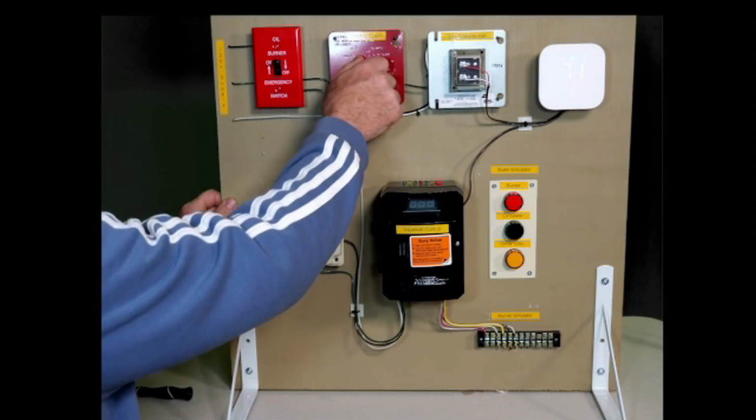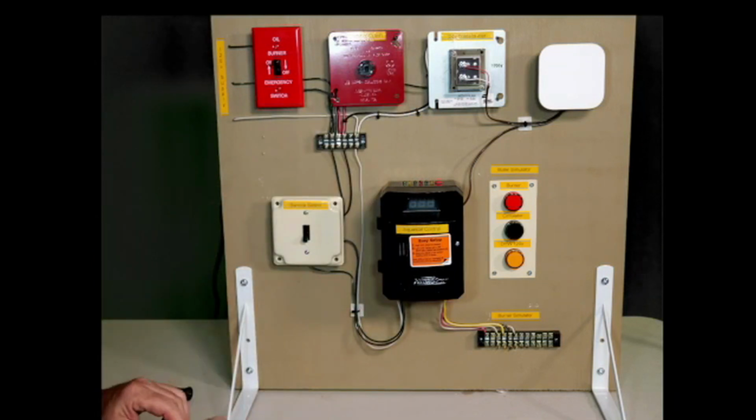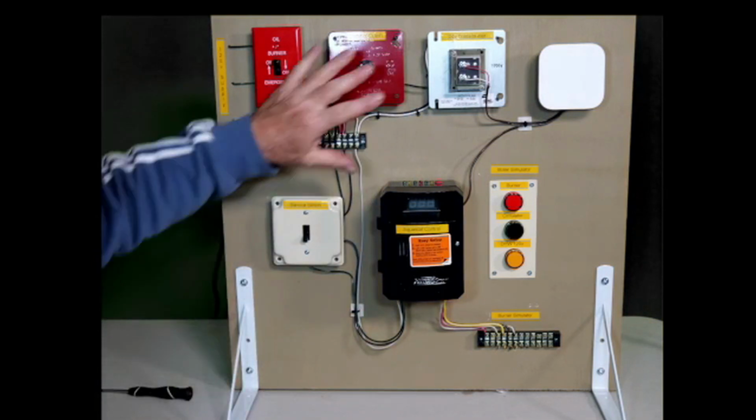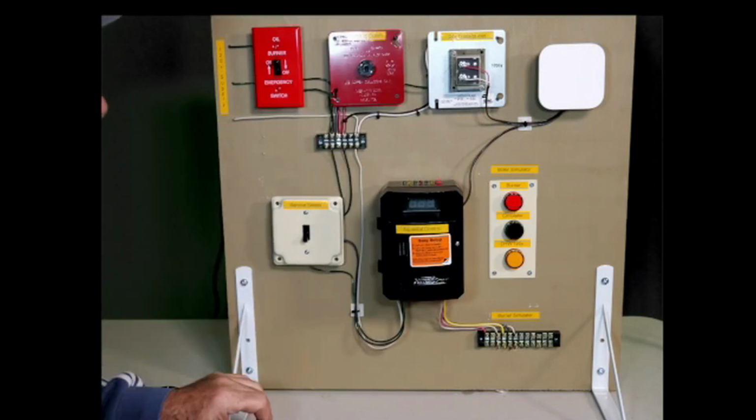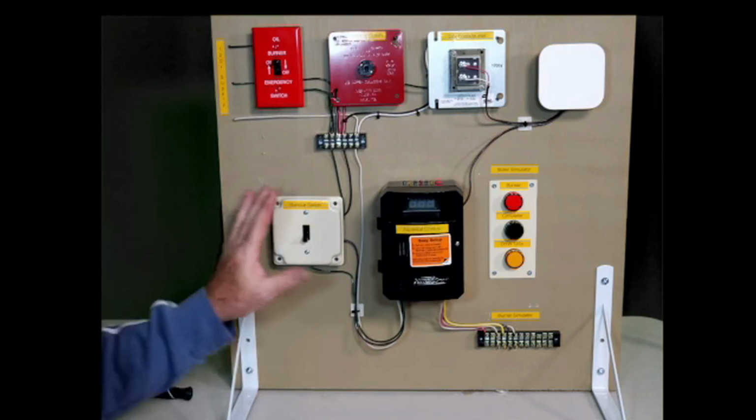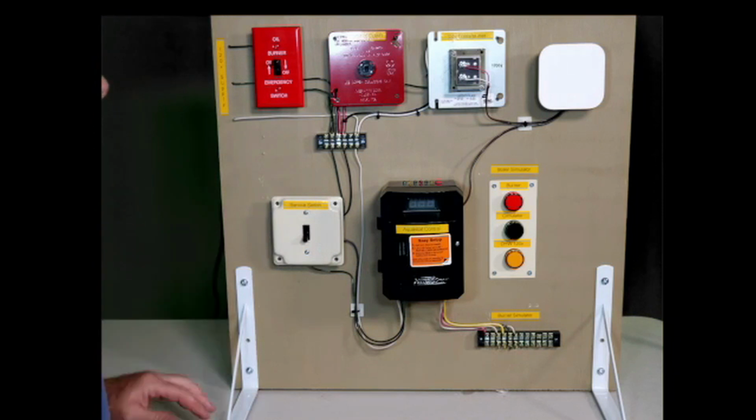I like to wire it so that when we remove the thermal cutoff, it shuts down the entire boiler circuit, the transformer, power to the service switch, any power to the burner. Make it safer for the technician to work on in case they're having trouble getting at the breaker panel, which is the case in some homes and businesses.